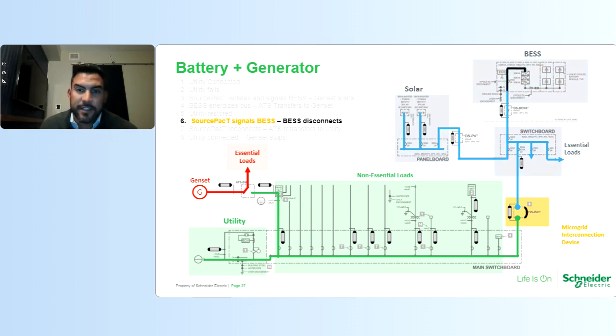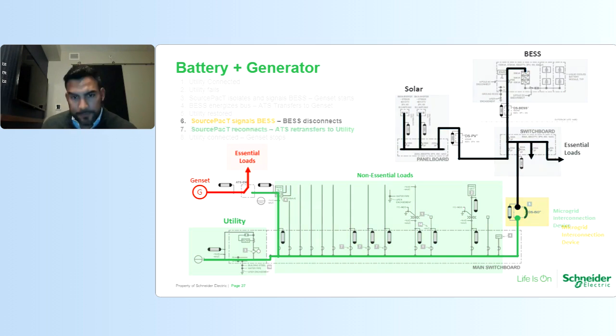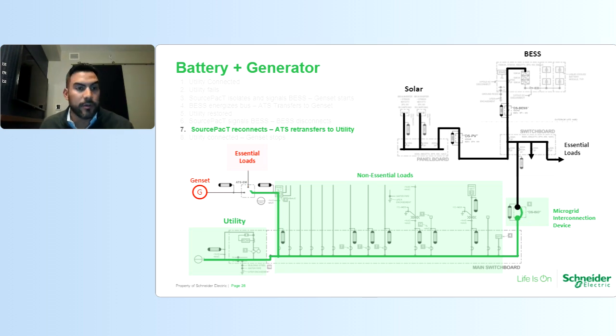SourcePacT is constantly monitoring the inverter-based power at the bottom of that breaker. Once it detects that the inverter-based power hits 50% of the nominal rating, it will close that breaker. Then once again, your energy storage system will come online, operating in a grid interactive mode. At the same time, the transfer switch will detect that utility has been restored. Depending on how you have that transfer switch configured, it could be an open or closed transition, hot to hot. It will transition back to utility.